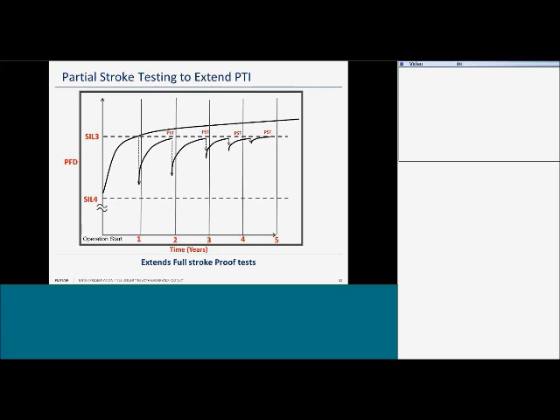So one of the portions of the standard tells customers a framework for stroke testing. So they know they have to stroke test, and it can become difficult to write procedures around stroke testing in some of the environments with our customers. For example, sulfur vapor recovery is not easy to shut that process down and bring that process back up. So one of the ways they can extend the proof test interval is by utilizing partial stroke testing.